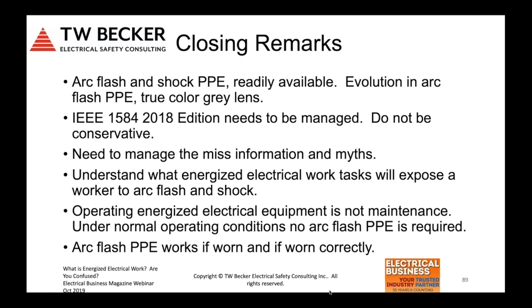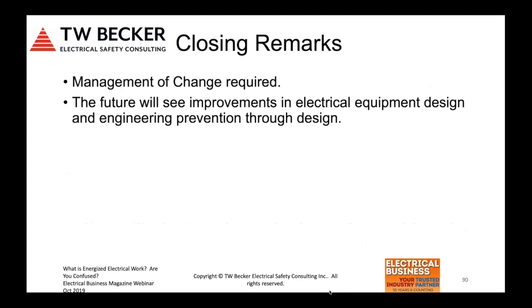So understand what energized electrical work tasks are and when a worker is exposed. Operating energized electrical equipment is not maintenance. Under normal operating conditions, no arc flash PPE is required. I know there's a lot of people out there that will not agree with me on that point, and I'd love to talk to them about it. Arc flash PPE works if worn and worn correctly. Management of change required. The future will see improvements in electrical equipment design and engineering, prevention through design.